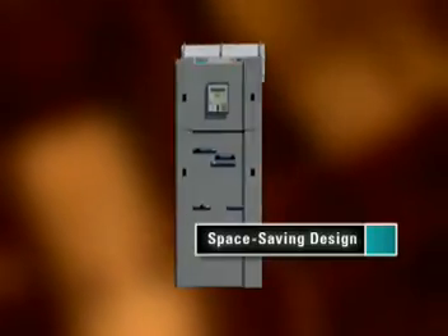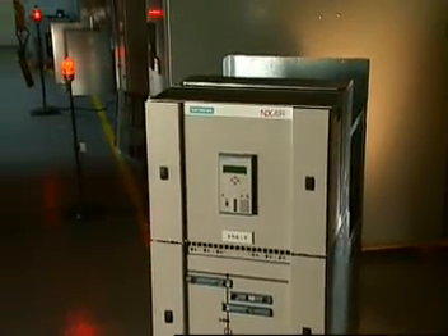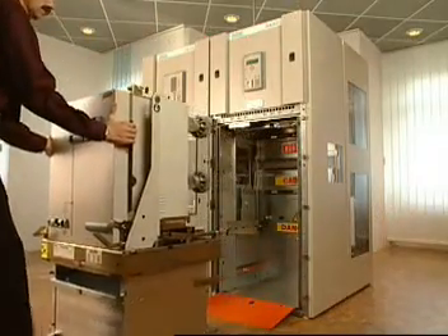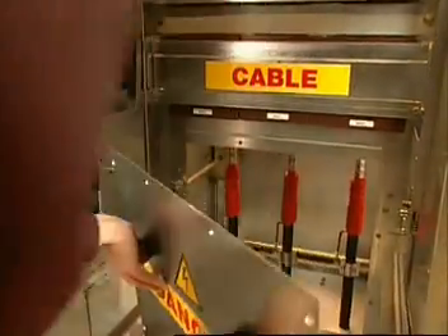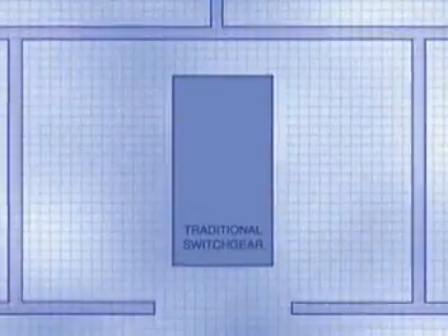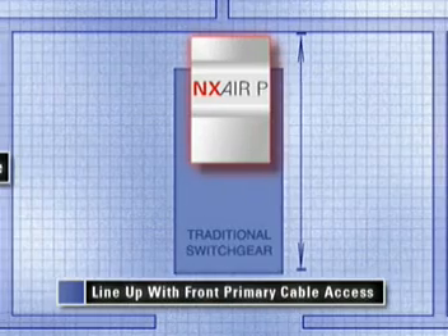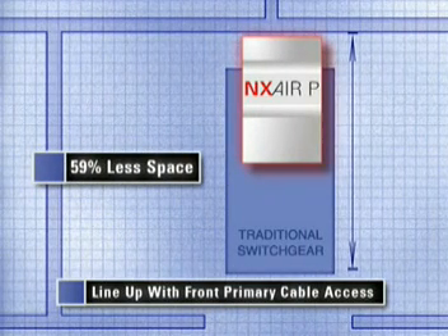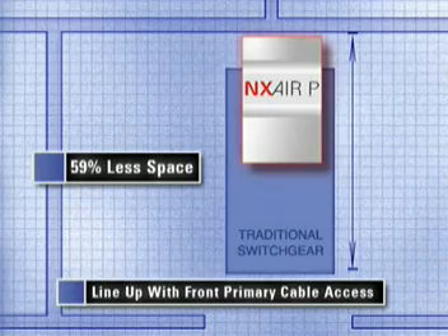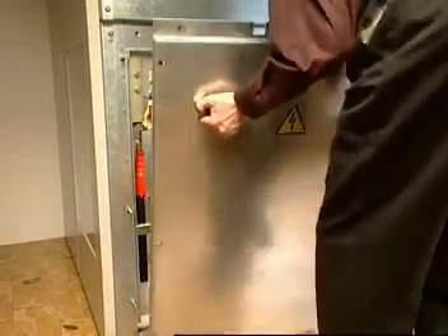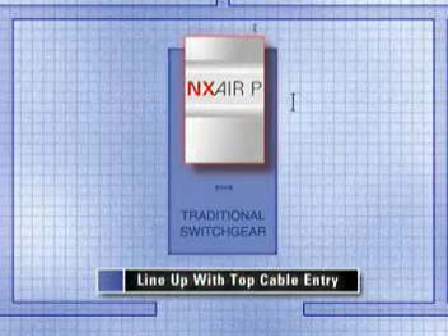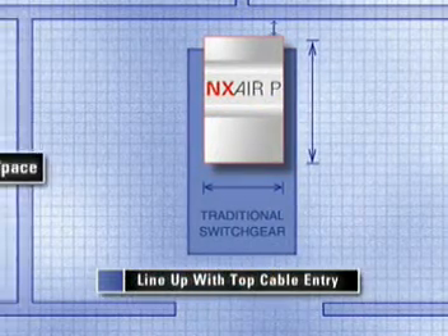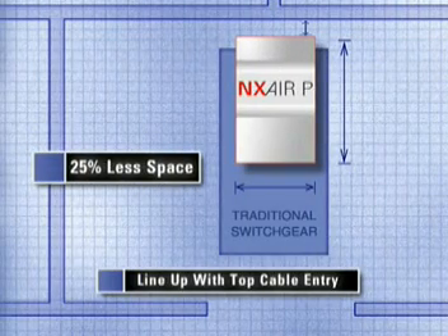The NXAirP's one-high design also offers space savings benefits. It is less wide than traditional switchgear, which contributes to its smaller footprint. It also features front primary cable access to allow the NXAirP to be flush mounted with the back wall. A back-to-back lineup with front primary cable access requires 59% less space than existing ANSI equipment on a per-section basis. That allows considerable space savings over traditional switchgear. If a job needs top cable entry, which would require an 18-inch rear extension, the NXAirP still uses 25% less space than existing ANSI gear. The NXAirP's fully functioning smaller design can translate into significant floor space savings.